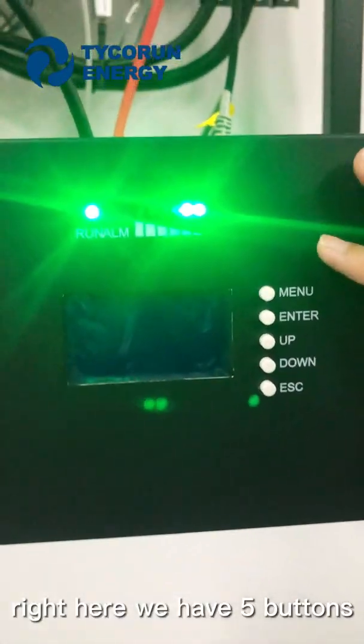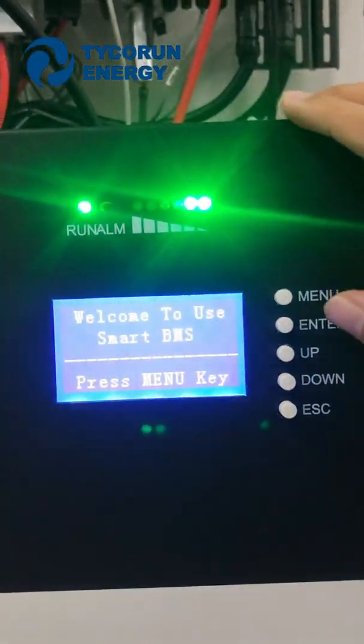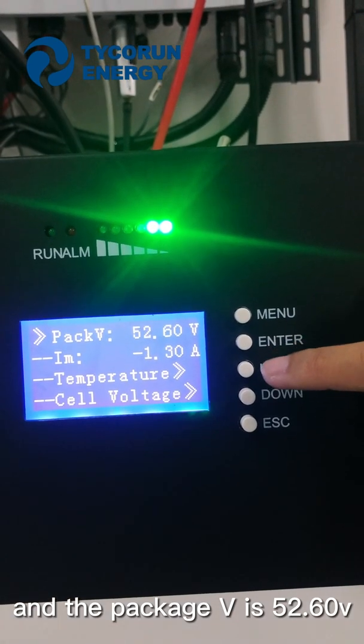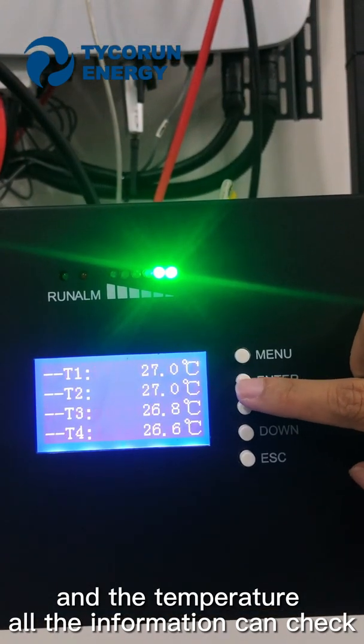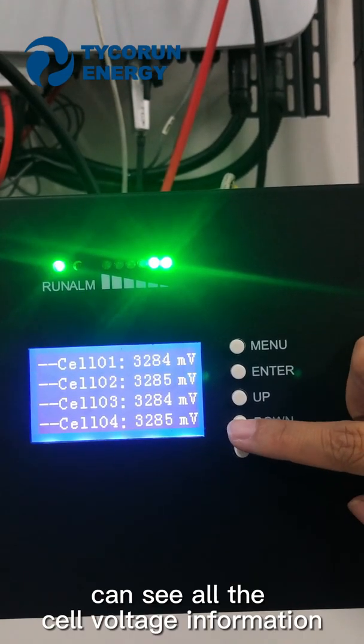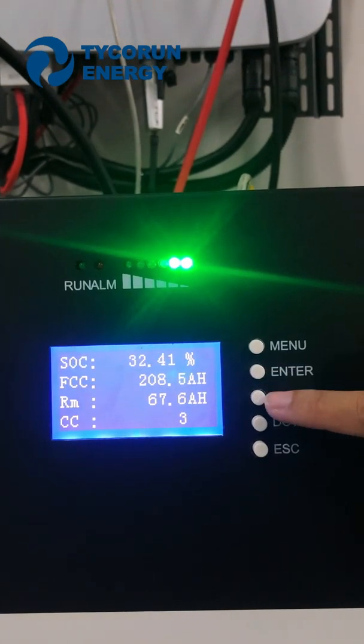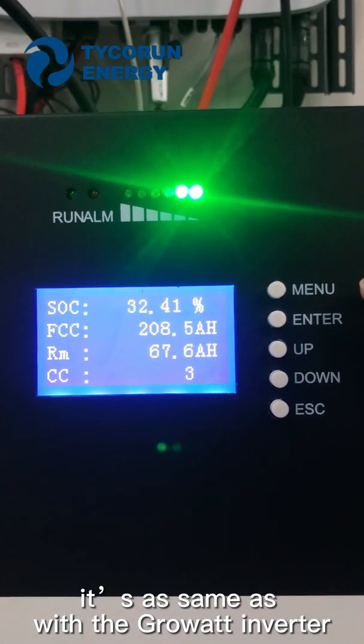Right here we have five buttons: the first one is menu, the second is enter, then up, down, and exit. The first menu is analog information. The pack voltage is 52.6 volts. We can check the temperature and all the information. And the cell voltage — you can see all the cell voltage information. The state of charge is 32%, which is the same as the Growatt Inverter display.